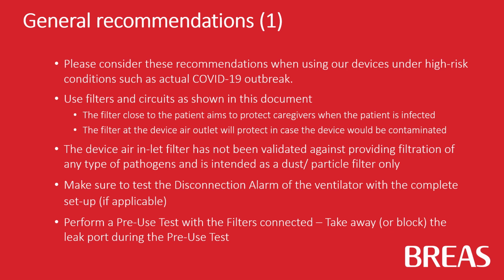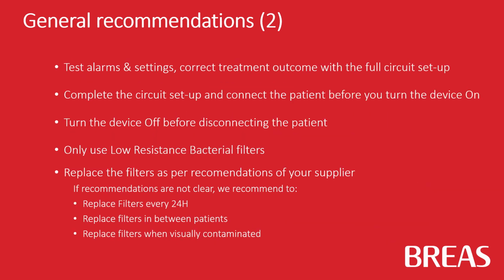Make sure to test the disconnection alarm of the ventilator with complete setup in case this is applicable. Perform a pre-use test with the filters connected. Make sure to take away or block the leak port during the pre-use test. Test alarms and treatment settings for correct treatment outcome with a full circuit setup. Complete the circuit setup and connect the patient before you turn on the device. Turn the device off before disconnecting the patient.